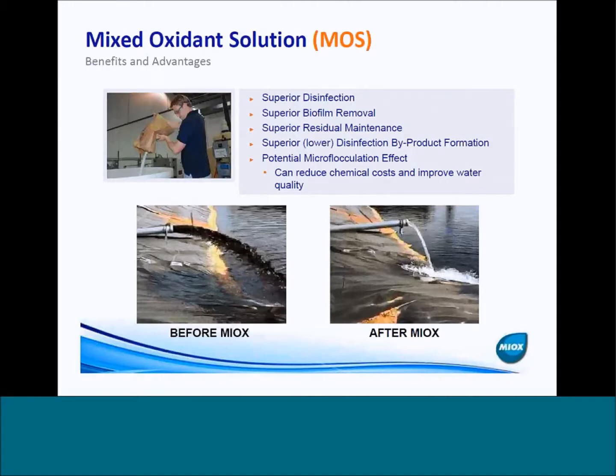From superior disinfection, it's not too far a step to think of getting superior biofilm removal, which we've seen in almost every application where we've installed a mixed oxidant solution generator and there has been biofilm present. Because you're able to strip out the biofilm and reduce your organic load, you're able to get better residual maintenance and lower disinfection byproduct formation. We've also observed a micro-flocculation effect when it's used in a flocculation process, which can greatly reduce chemical costs and improve water quality — an additional benefit of the optimized mixed oxidant solution chemistry.